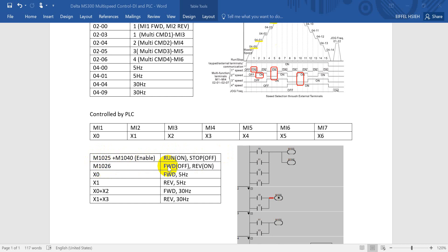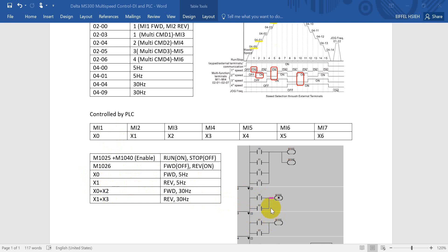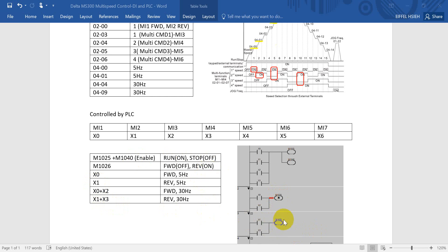Then M1026 is for the direction control. X0 means MI1, this is for forward 5 Hertz. X1 is for reverse 5 Hertz. Basically here you can see for X0 and X2, this one is for forward, so we have to reset M1026. For X1 and X3, this one is reverse, so we have to output control M1026.